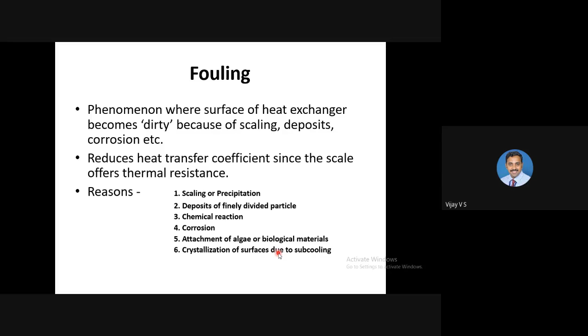The reasons for fouling are many. It may be scaling or precipitation, or deposit of finely divided particles, or even a chemical reaction. Corrosion may be one more reason. Attachment of algae or biological material. And crystallization on surfaces due to subcooling. This is possible in refrigeration and so on, when the cooling is very high. So many reasons are there.